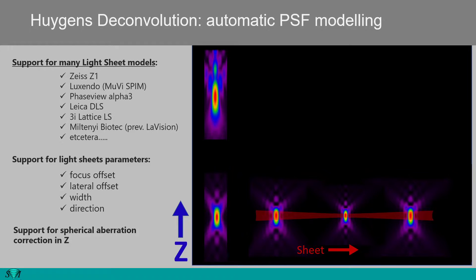Huygens deconvolution automatically takes into account different modes of illumination and sheet geometries. It also takes into account both spherical aberration along the optical axis and the variation of the point spread function with the thickness of the lightsheet. Therefore, many models of lightsheet microscope, including the most common commercially available as well as custom-built ones, are supported.